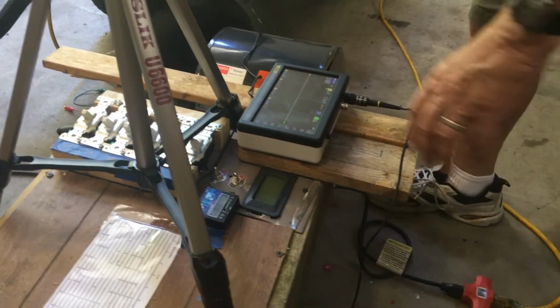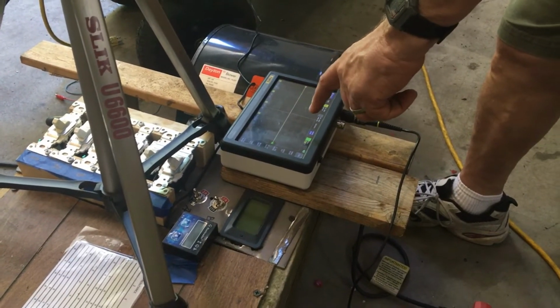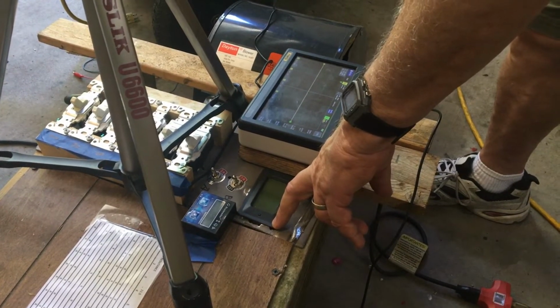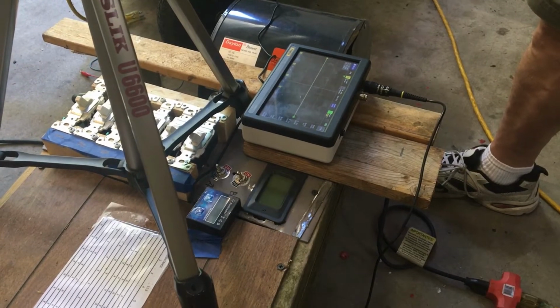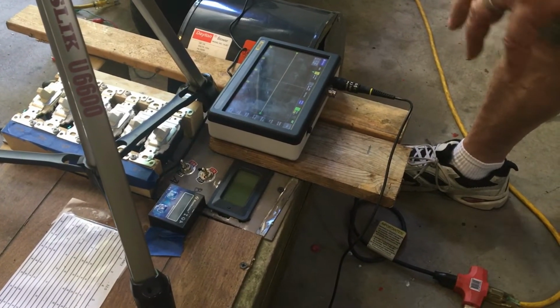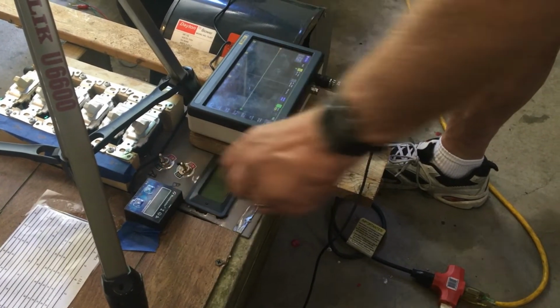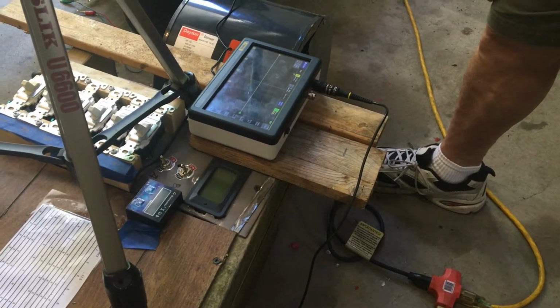I've got an oscilloscope here which should show the waveform coming off of the generator. We've also got a power monitor here which will give us the amps, kilowatts and voltage output. It also has a small readout that indicates the frequency. I would say ignore that. It's just a flag really. It either flips to 50 or 60. It doesn't give the exact frequency. And last but not least, I've got a small inductive tachometer here so we can keep an eye on the engine speed.